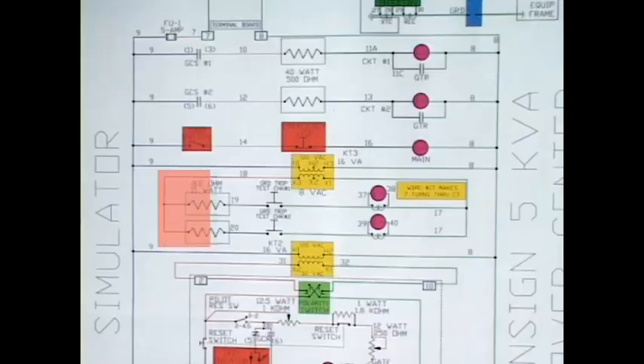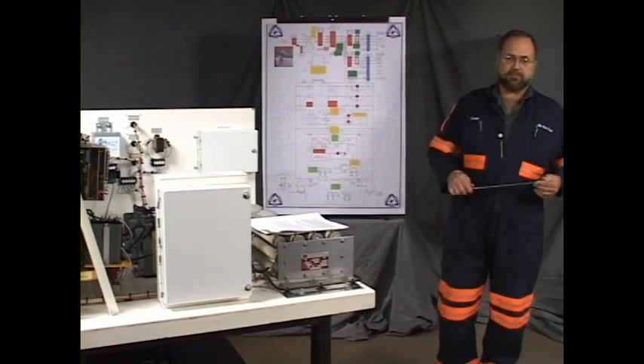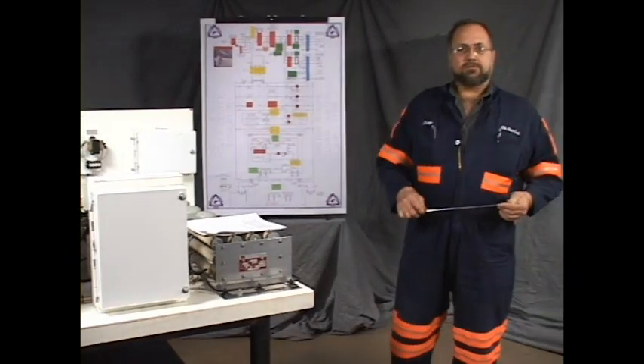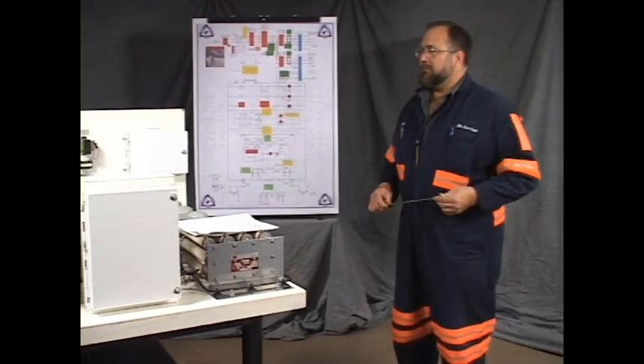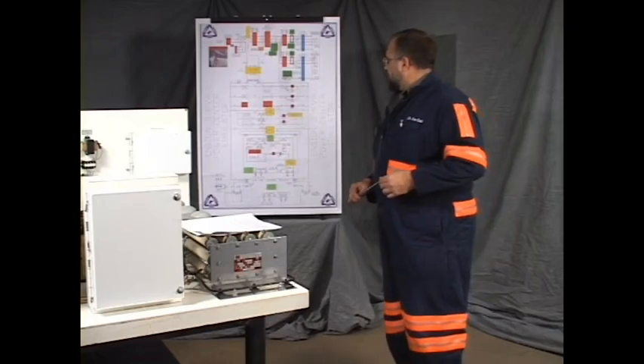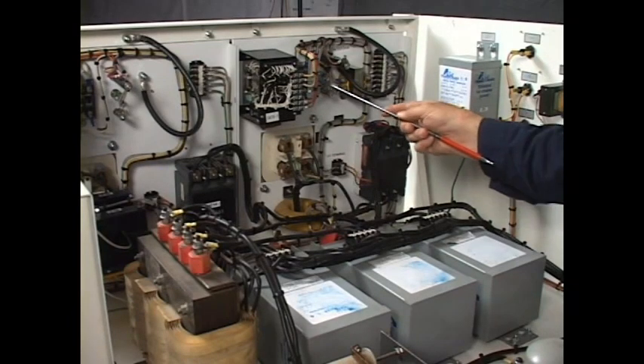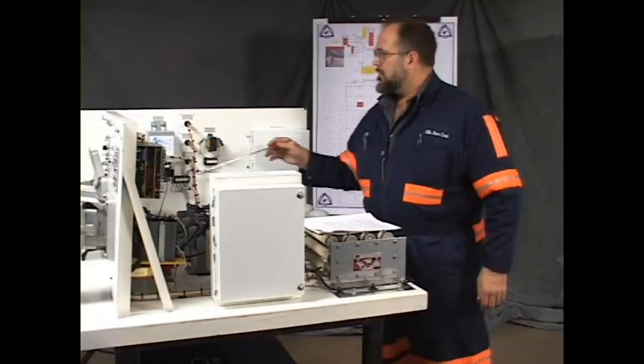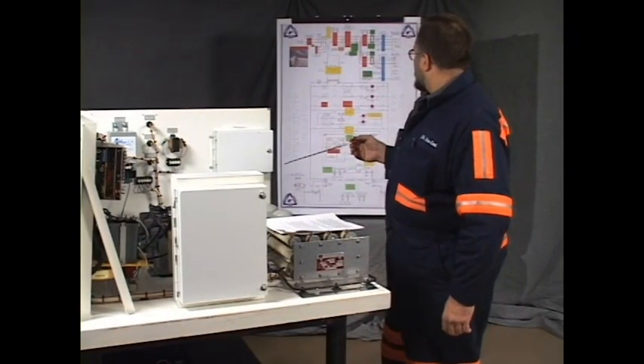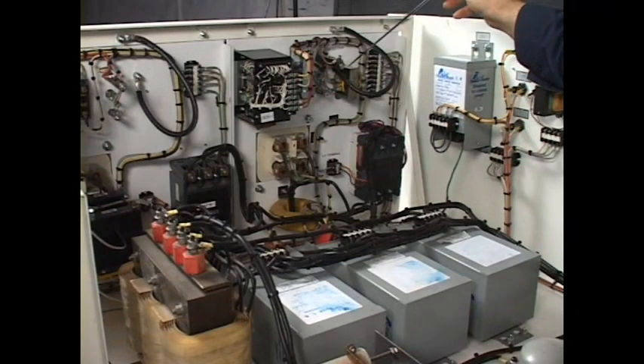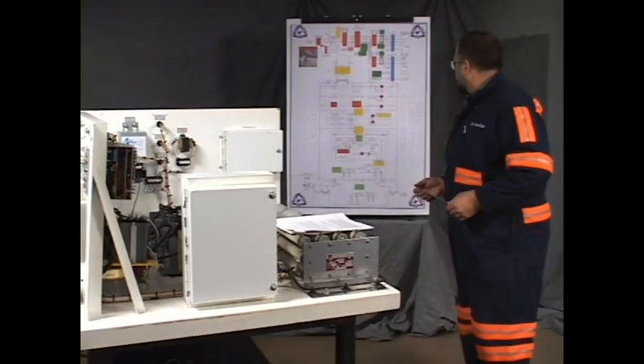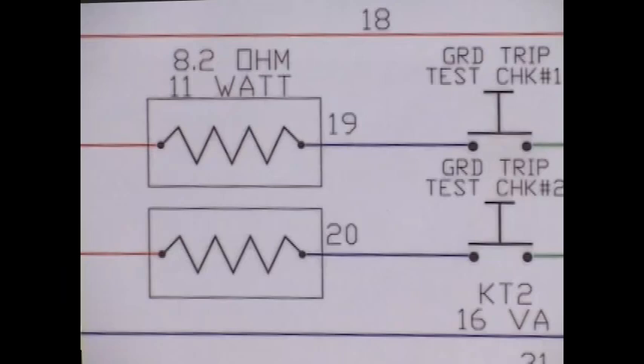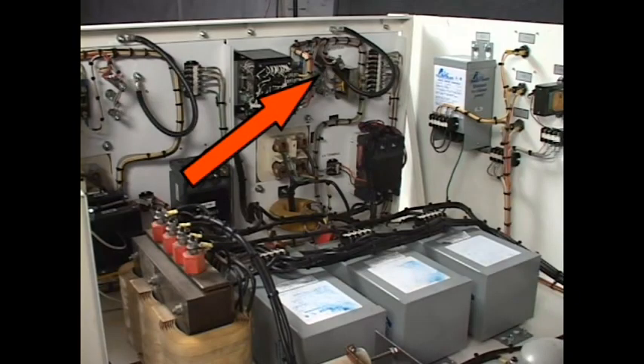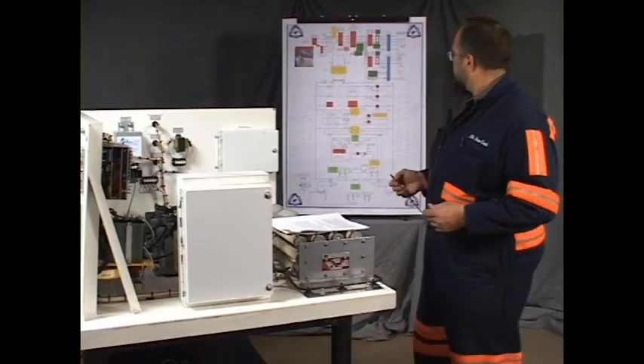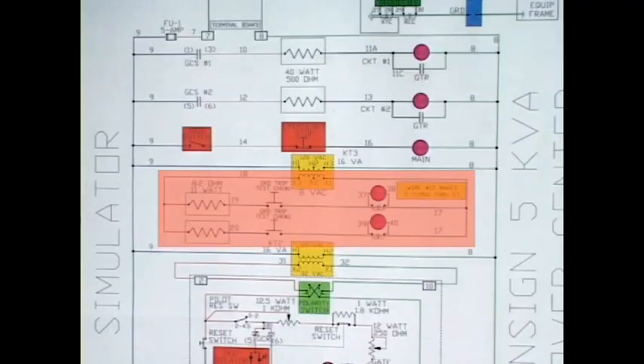This part of the circuit is the testing circuit for the ground trip test, to assure that the function of the ground fault circuit is intact. It's a test that's required by the government that you administer regularly. And the ground trip test switch is located on the back of this panel right here. And the small transformer that supplies the power to operate this circuit is right here. It's listed as KT3. There's an 8.2 ohm 11 watt resistor located directly adjacent to the transformer right there. And the rest of that circuit is wire.